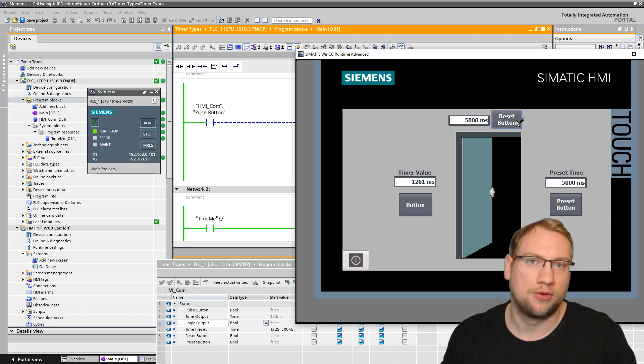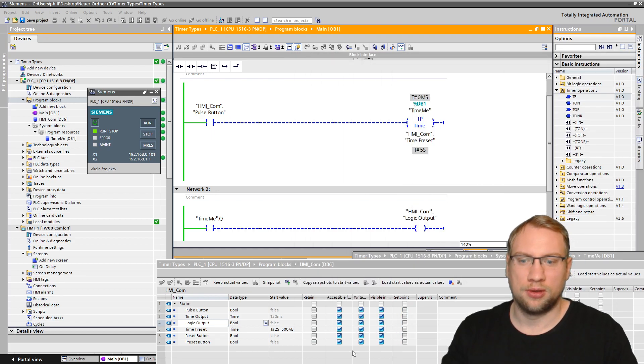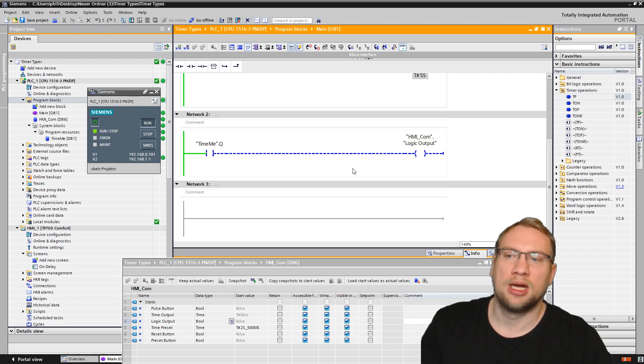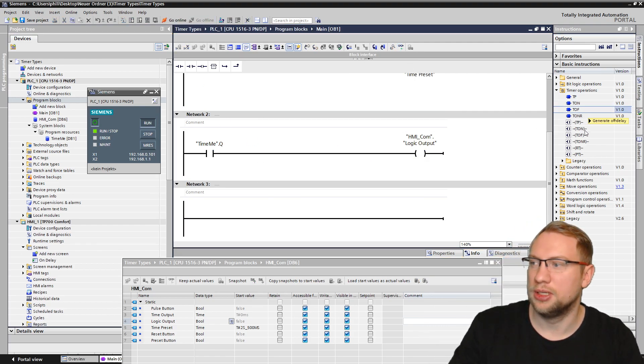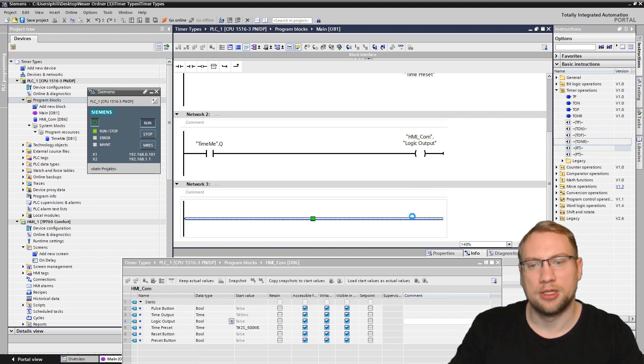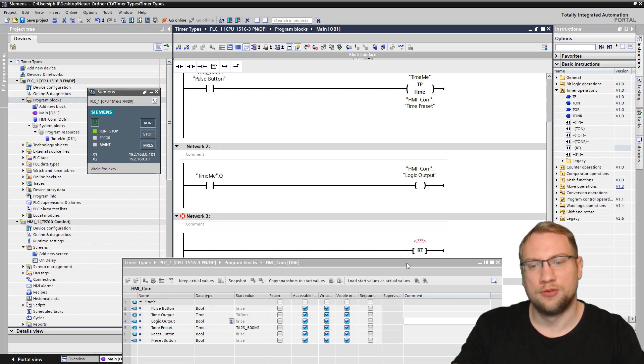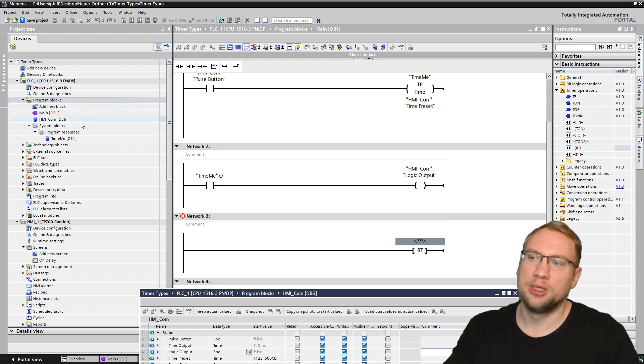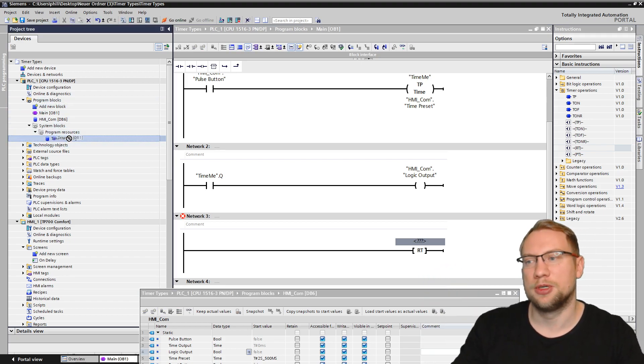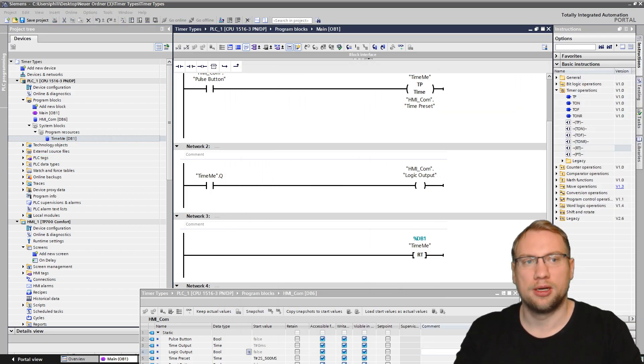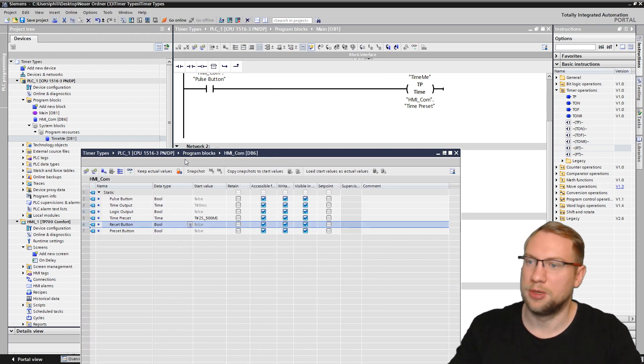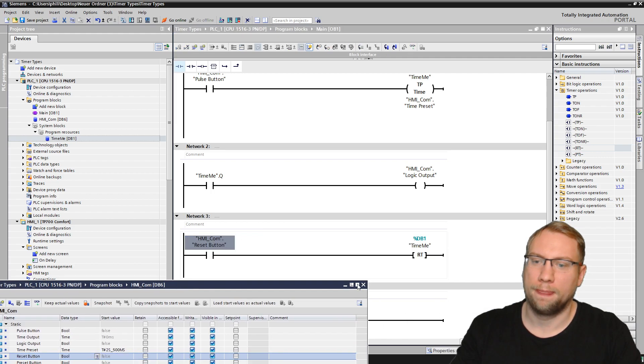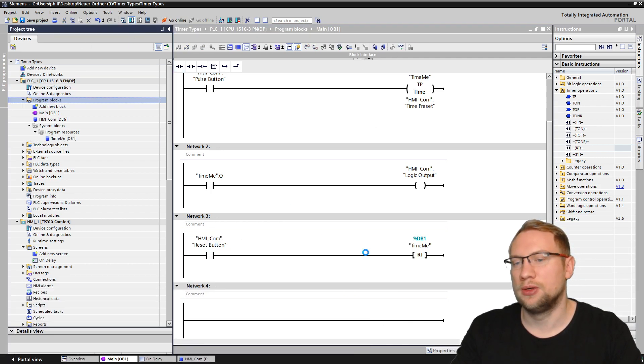This one I have linked again to my data block here, to my HMI data block. And there is now an instruction here in the list. This instruction is called RT. RT means reset timer. So I will use that reset timer instruction here. See it? The reset timer instruction to reset the timer. What do we need to put on top? We will need to put our timer. The data block here is our timer. So I will just drag and drop that timer here. When do I want to reset it? When this button is pressed. This button I have already linked to my program here. I think I called it reset button. Let's download.